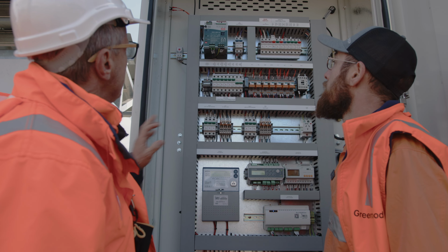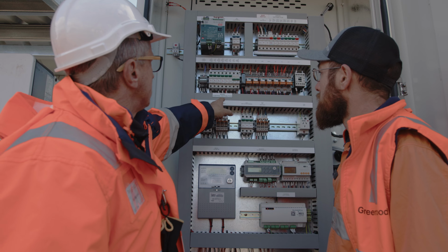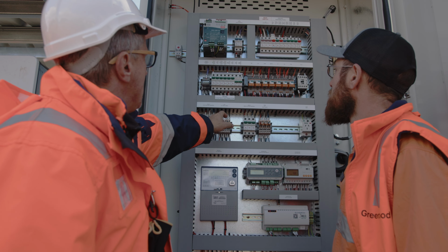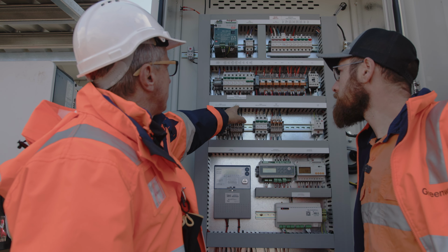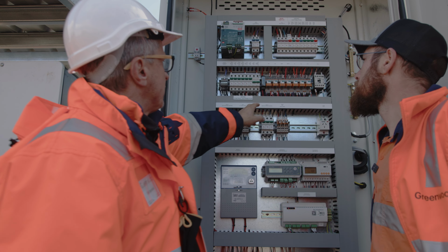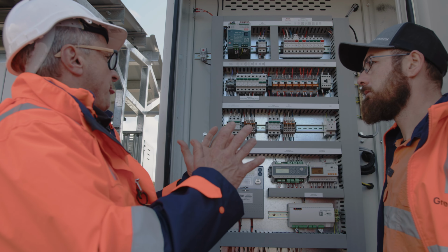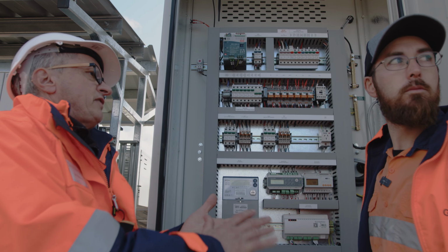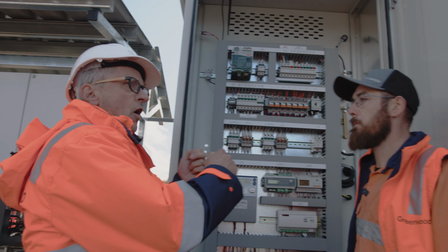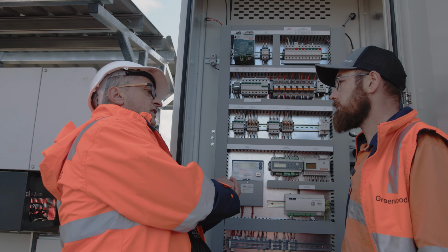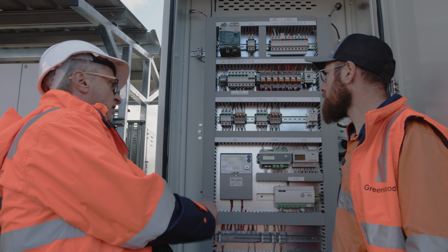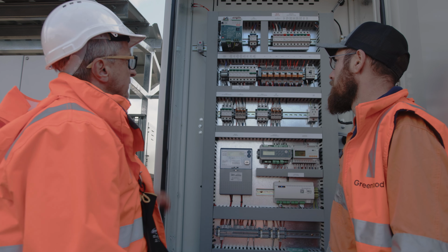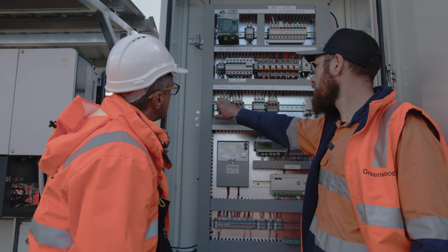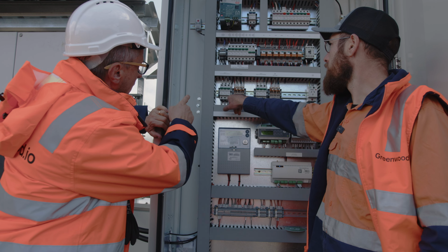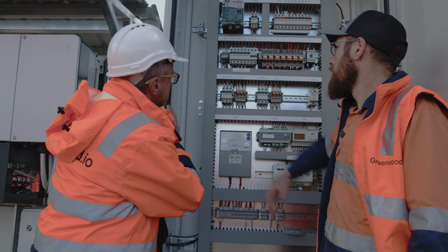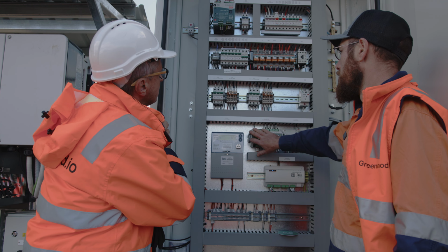And you've got here your 24 volt DC control distribution. You've got your CT test links. I haven't been on site when they've done secondary injection testing. When they come to do secondary injection testing on the site, where are they putting their probes in? Right, so pretty much they will disconnect this breaker and they'll connect in most likely at the bottom of this one, to supply voltage back to our mains probe.